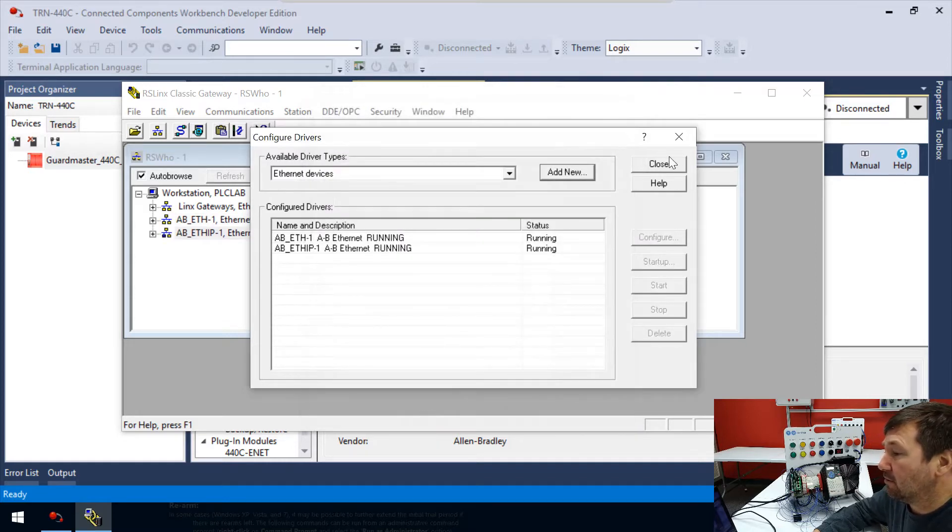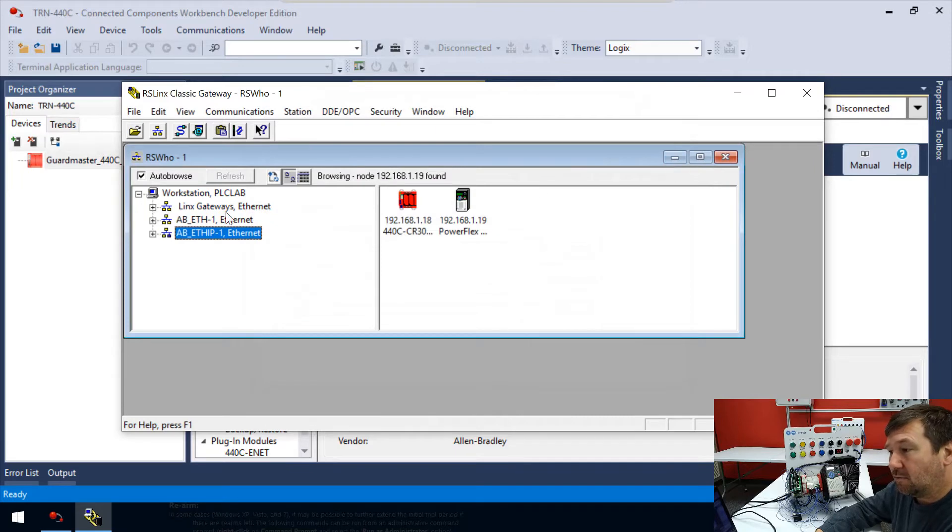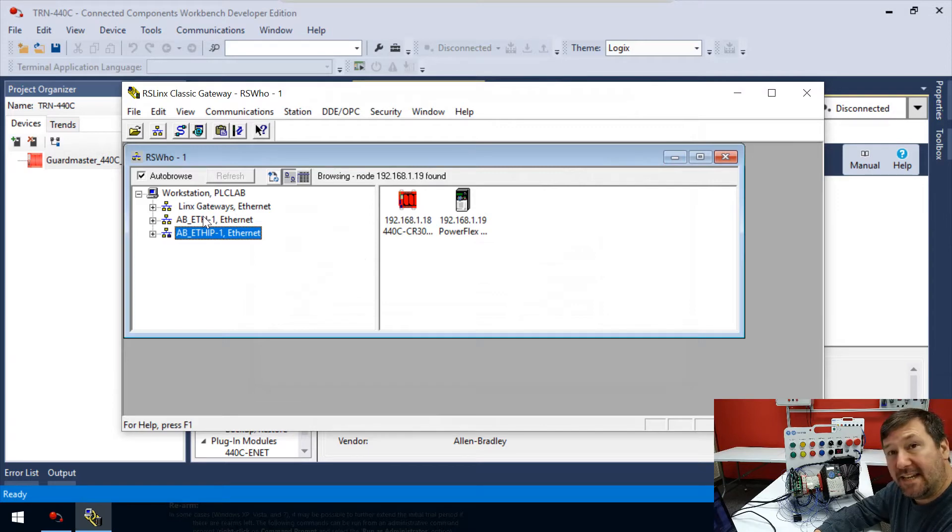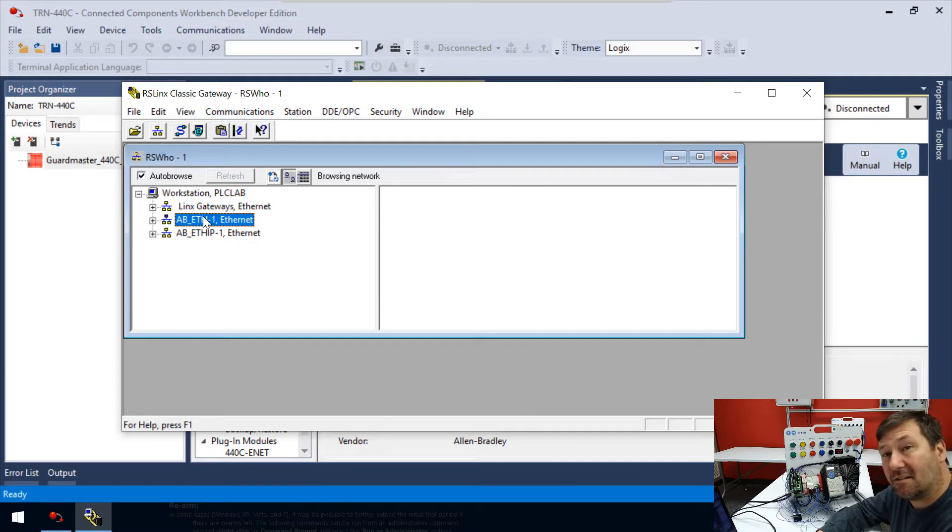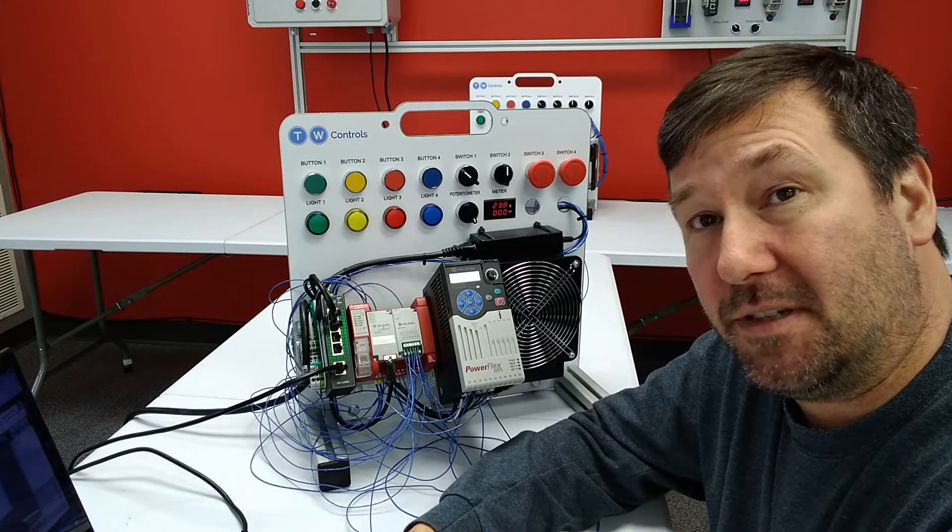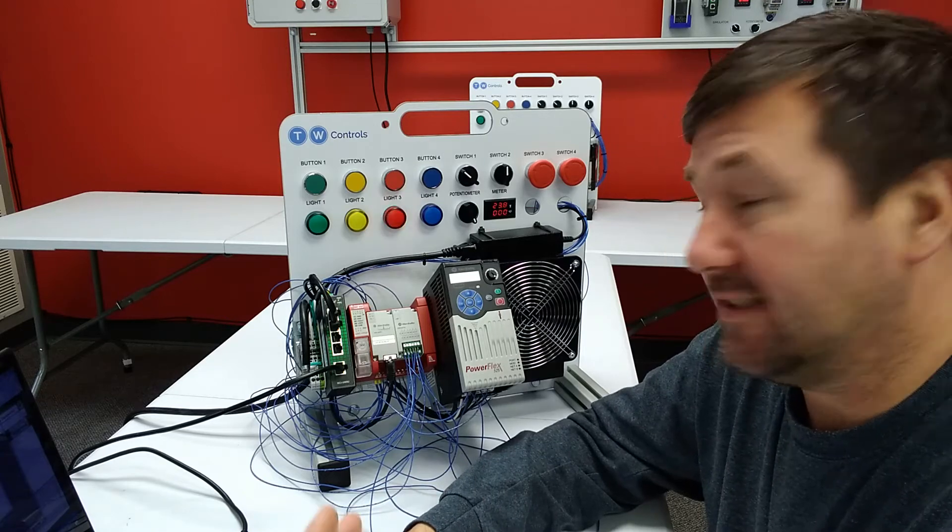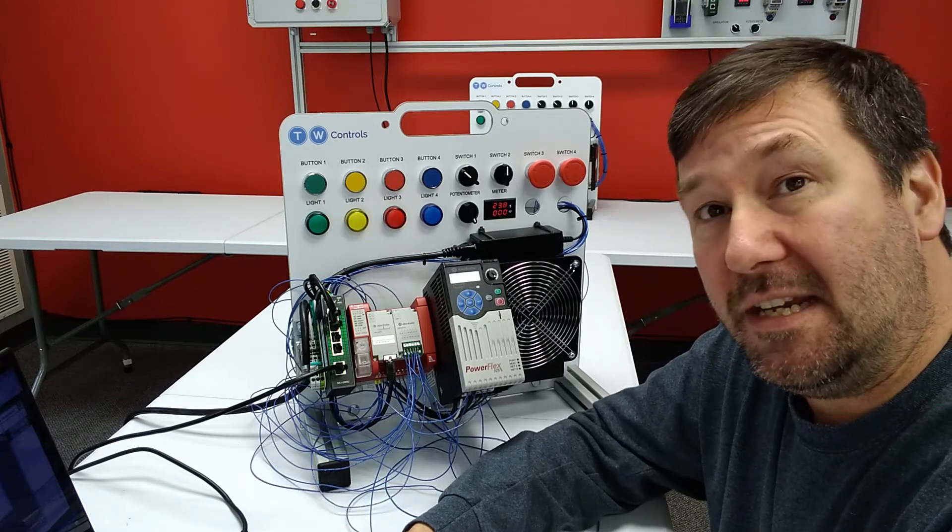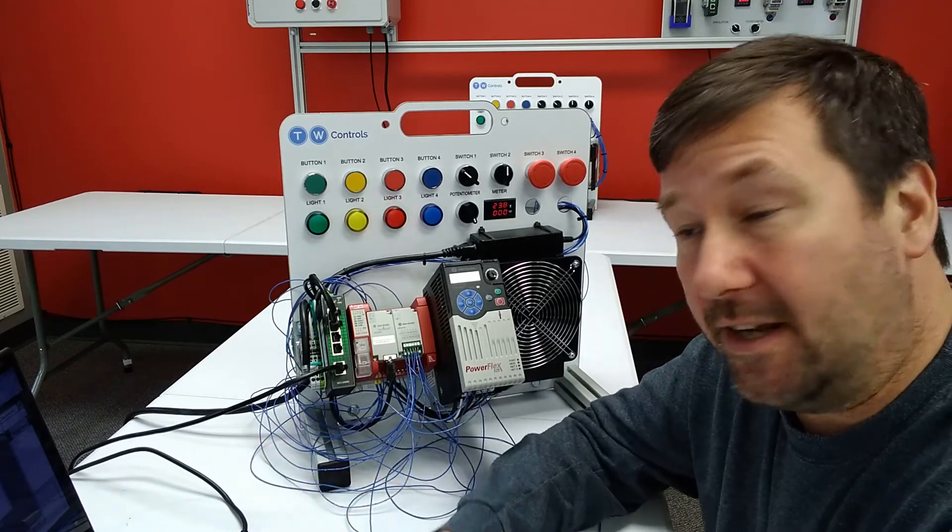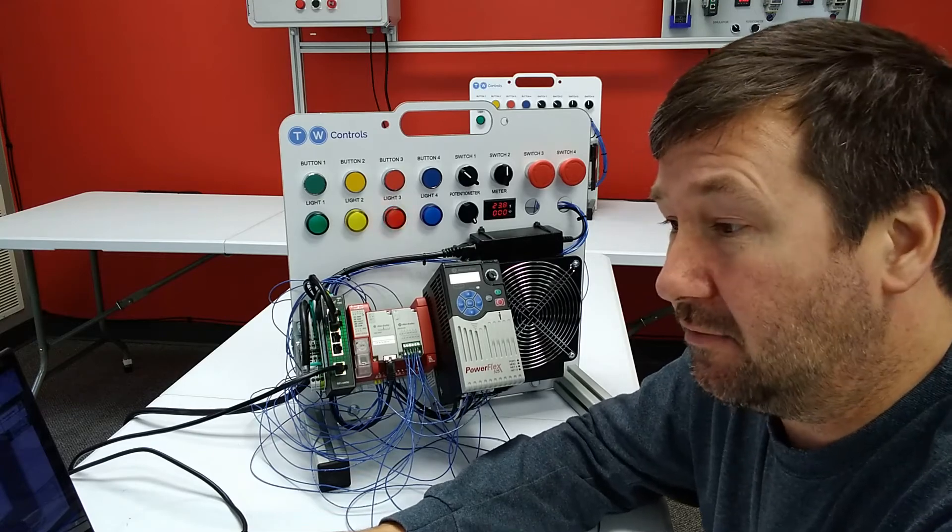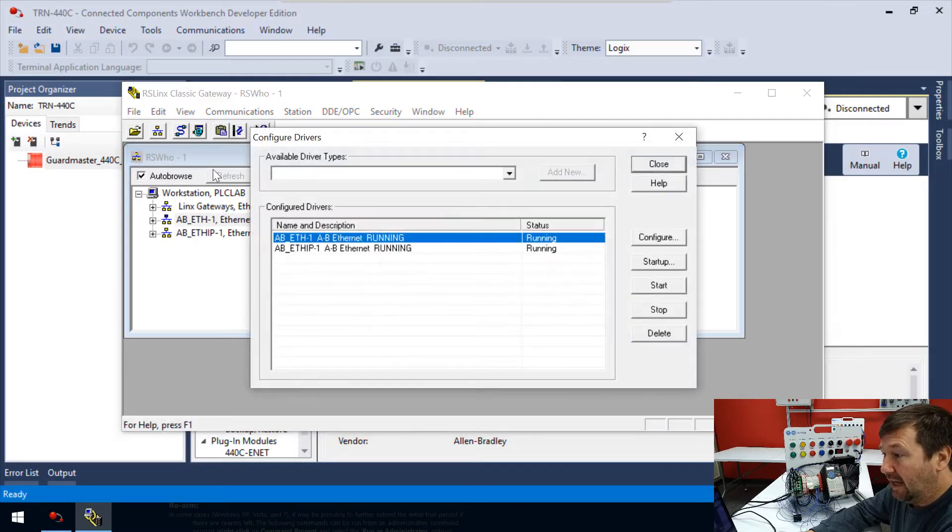We'll click Close. Our Ethernet IP driver went out and found them. When we click on our AB-ETH-1 that we just created, it's just going to look like this, and as long as you wait, it's going to still look like this. That's the difference between the two drivers: the Ethernet IP can discover devices, but the Ethernet Devices driver, we've got to tell it what to go look for.